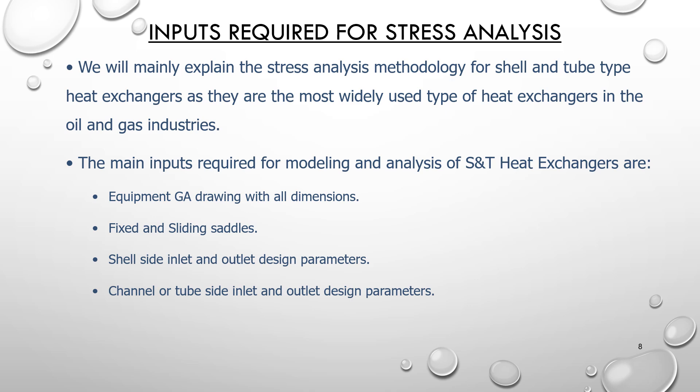Now, inputs required for stress analysis of shell and tube heat exchangers. The main inputs required for modeling and analysis are: the equipment general arrangement drawing with all dimensions — from which you obtain dimensions of each element including nozzles, shell part, and channel or tube part — as well as design parameters and materials.